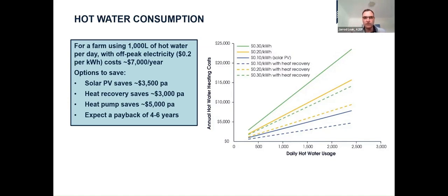You could do heat recovery, and that'll reduce about 40% by recovering heat, say, from your refrigeration system. You could do a heat pump, and as Gab mentioned, about 75% or so reduction there. So there's a nice return there. Overall, you'd expect around 4 to 6 years, give or take. It's unusual that you'd be less than 1 or 2 years payback, but think about 4 to 6 years, which is still a pretty reasonable rate of return. There's a nice little graph there you can follow. You might be on the solid line, and then you can move down to the dotted line with heat recovery, and then you can calculate your savings for whatever your hot water usage is.